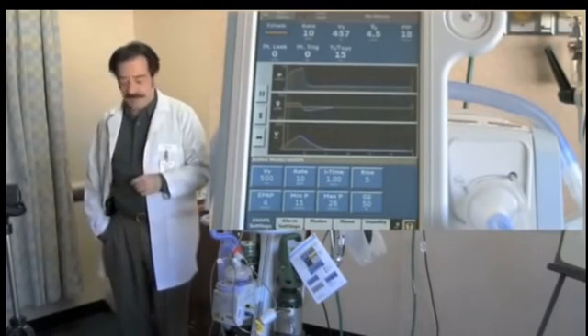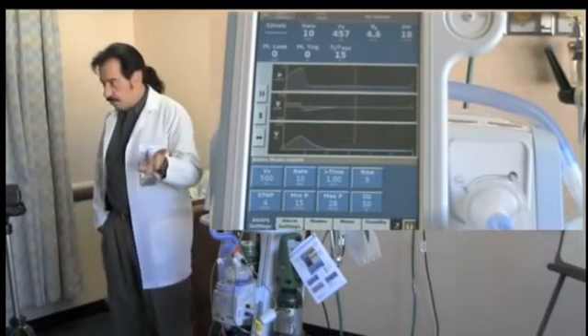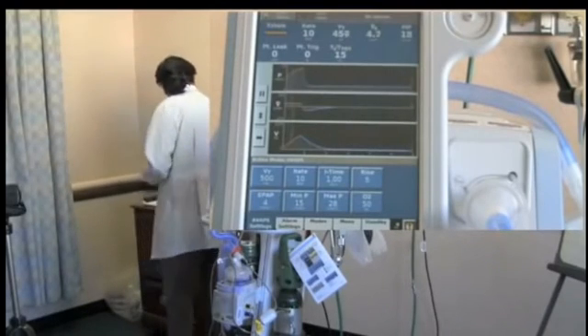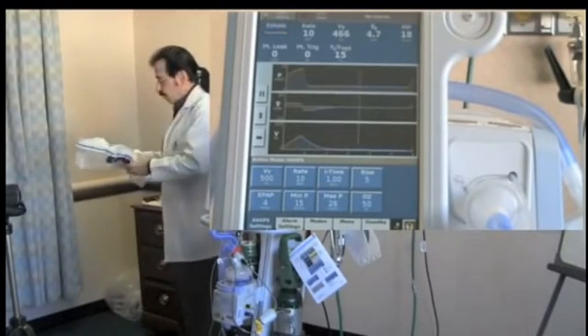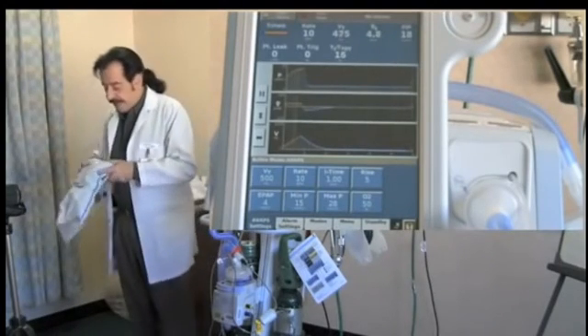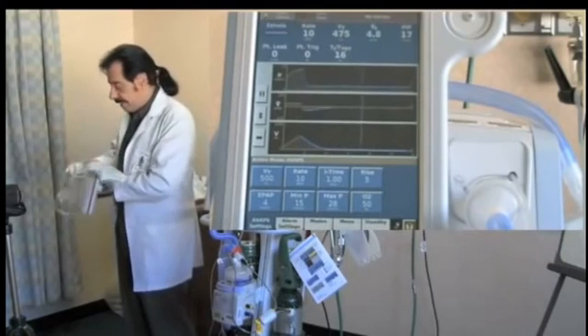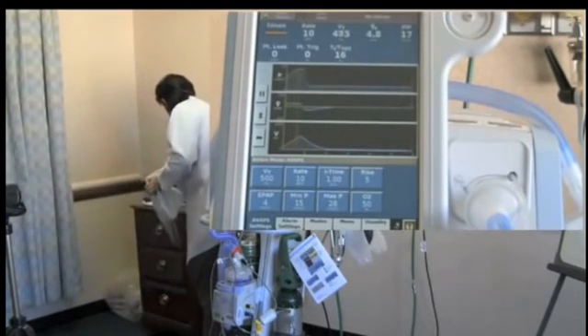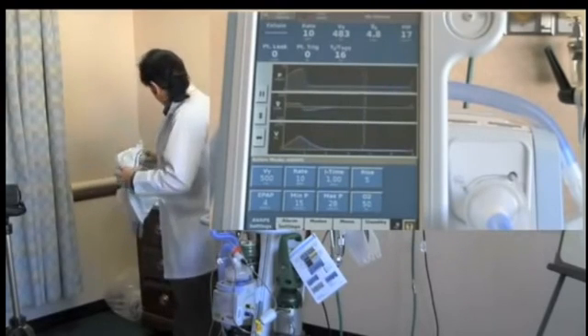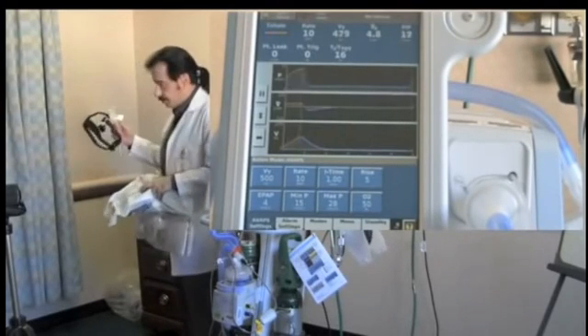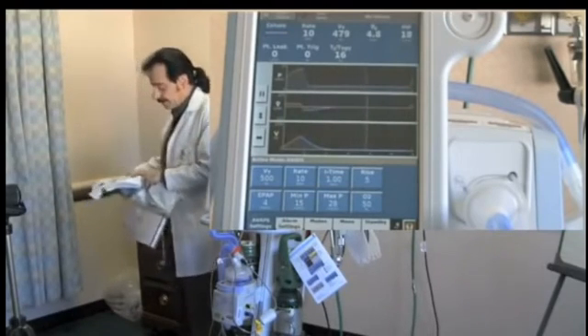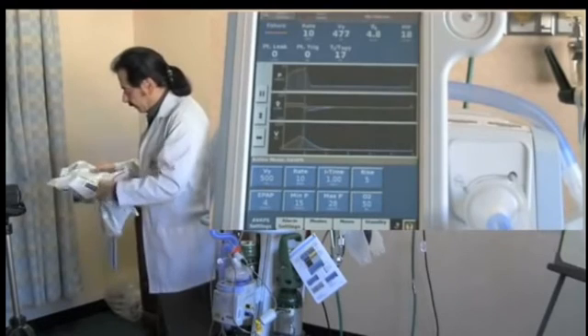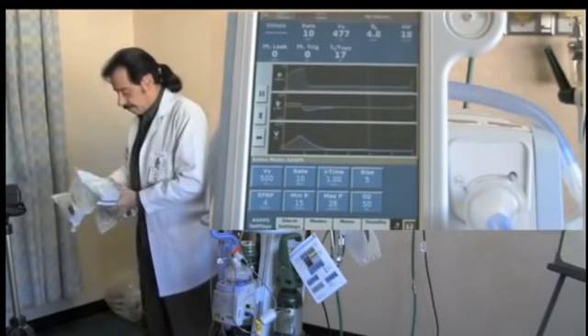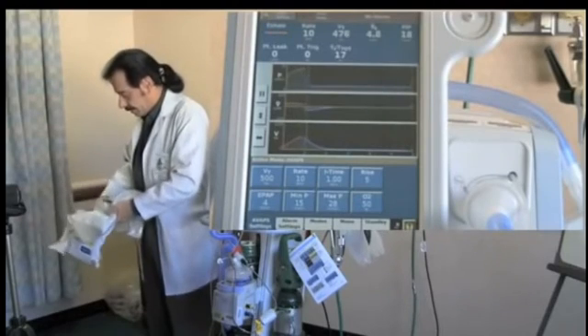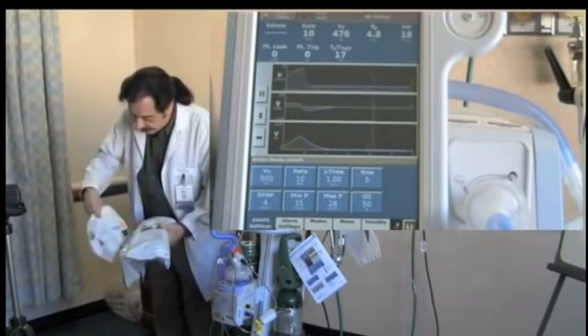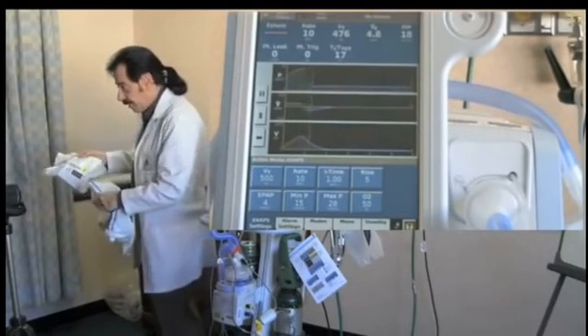Now, when you start the therapy on the patient, you've got to put them on an interface, on a mask, okay? The Respironics systems would prefer that you use a Respironics mask, of course. And regardless of what size this mask may be, this is a medium full face mask. Here's a small nasal mask, okay? And here's a kind of an alternative to prongs, okay? Cannula type interface. But regardless of the size of the mask, they all have a number on them. So don't throw the bag away until you look for the number, okay? In this case, it's the number 1, and it's the number 1 on this one, okay? So they both have the same number.